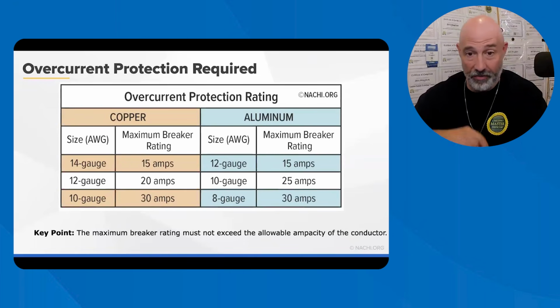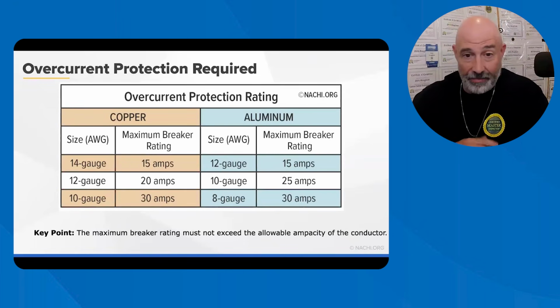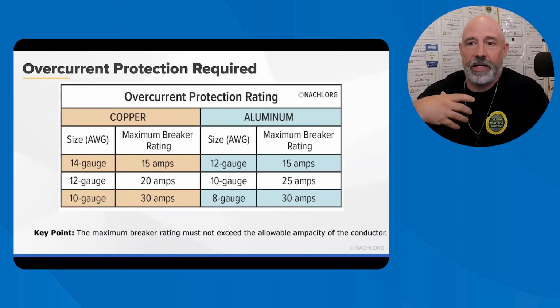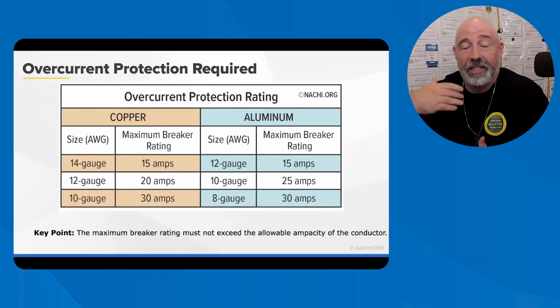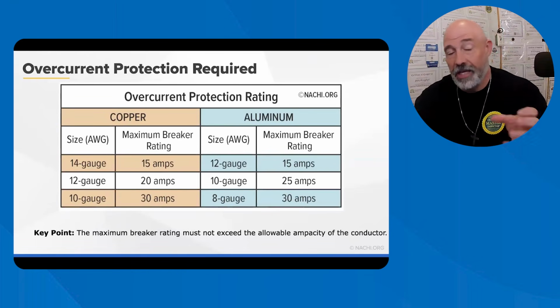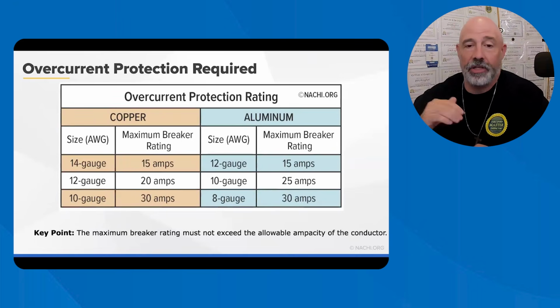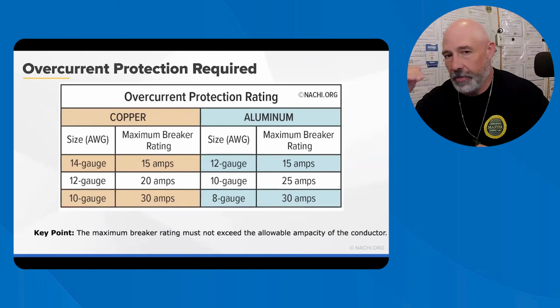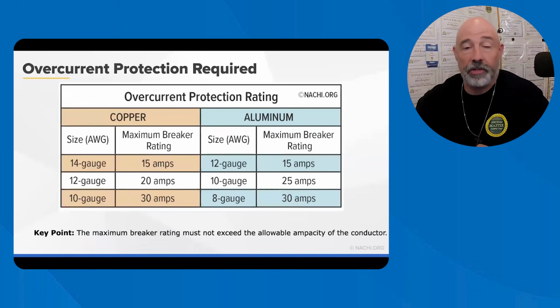The key point: the breaker size should never exceed the ampacity of the conductor it protects. So 14 gauge, 15 amps; 12 gauge, 20 amps; 10 gauge, 30 amps, and so on. The American Wire Gauge, the standard sizing system for electrical components, is always going to be in your brain when you're taking off that electrical panel cover. Like I said, I start with the smallest and work my way up. I look at the 15 amp, size that wire in my head, and then I can go, oh, that's a 12, that's a 10, and so on.